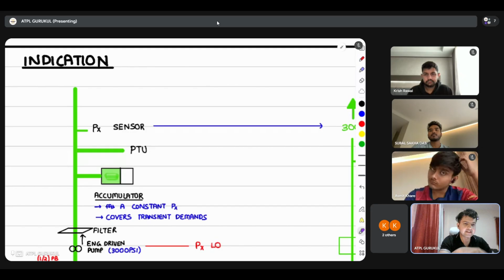हाँ, once it has delivered it for about a second and a half, till then the swash plate of this engine driven pump will go to the maximum stroke length and it will start giving you the pressure which is desirable by the system. So whenever the pressure demand is a transient demand, it will cater to those transient demands and maintain a constant pressure there.